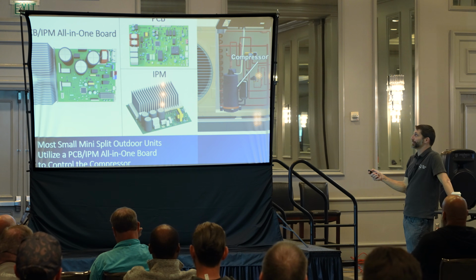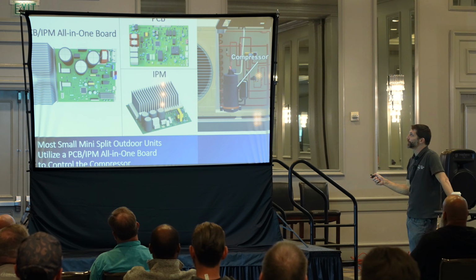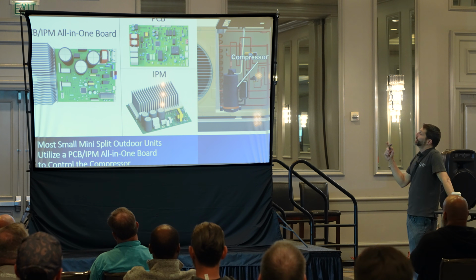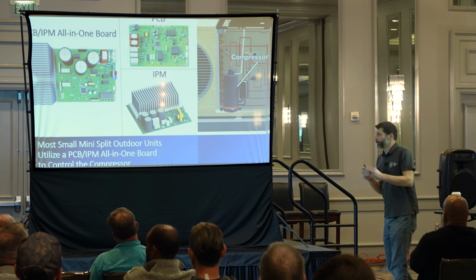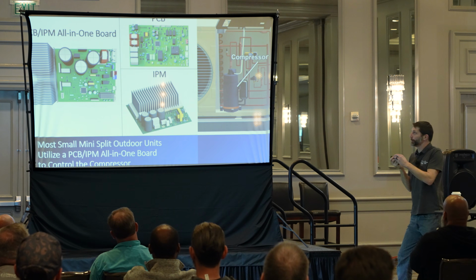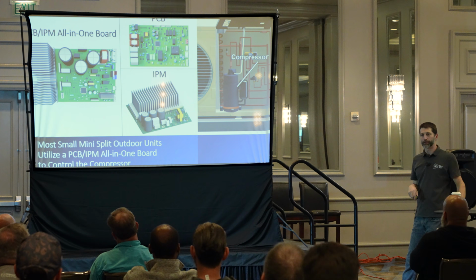So you've got to think like that. That's a lot going on, and we're trying to understand how these systems work. They're changing the pumping speed of the compressor and also the hole size in the EEV, potentially every 20 seconds to 2 minutes.